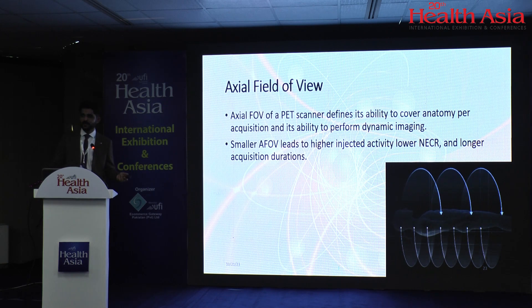Another important factor is axial field of view (FOV). Besides scanning, production and consumption of radiopharmaceutical pose significant demands. A smaller FOV PET-CT needs more time to acquire one patient. An extended FOV PET-CT shortens acquisition time and also reduces the amount of injected radiopharmaceutical. For example, a PET-CT with an axial FOV of 20 cm must acquire eight bed positions from skull vault to mid-thigh — about 18 minutes — whereas a scanner with an axial FOV of 30 cm requires only three bed positions — about six minutes.